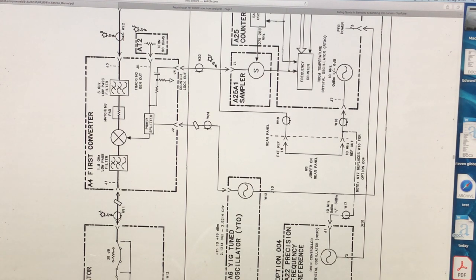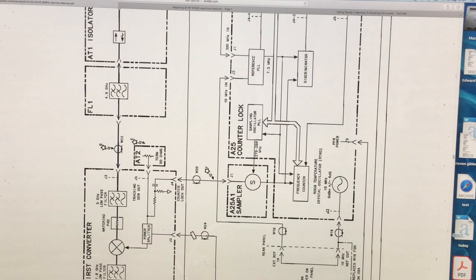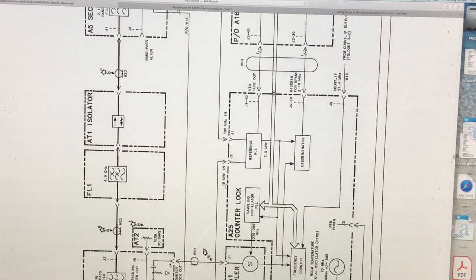So we've got what appears to be on W15, I think it is, coming in here, the frequency tune for that, which is what we were faffing about with the DAC. There we've got a 10 megs output by the SMB connector, 0 dBm, which is what it should be. It looks like it breaks out into two places, goes into the A25 counter lock, as well as coming out on a secondary, then all the way along here.